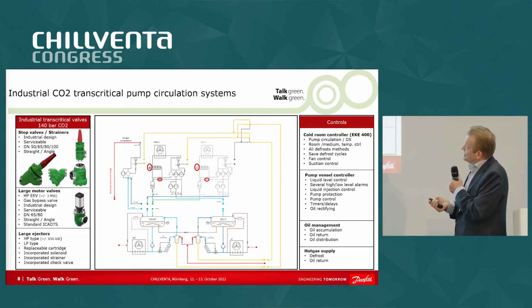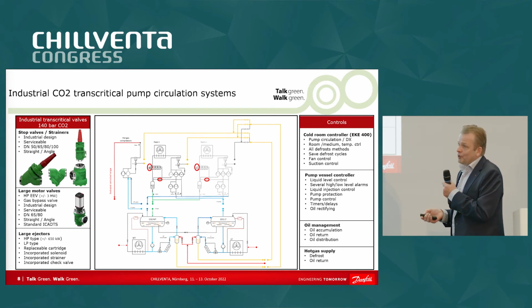And especially if you are in a transcritical state, we all know that the amount of flash gas that you create is quite high. And then you need big gas bypass valves here to get rid of this flash gas. That's what this valve is going to be. So for the expansion valve, we can do 2, 3, 4 megawatts, something like that. And for the gas bypass valve, we can do probably half of that. So this was a valve that was really needed to support these larger systems.